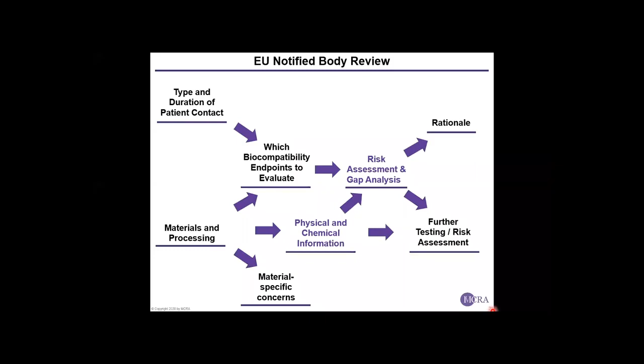Additionally, and this is a really important point that comes up for folks that have experience with the US FDA, it is likely insufficient for you to just conduct the standard battery of biocompatibility tests to satisfy European regulators. Instead, we anticipate that you'll need to be looking at your materials and your processing and providing those unique elements of evaluation that the notified bodies are looking for.